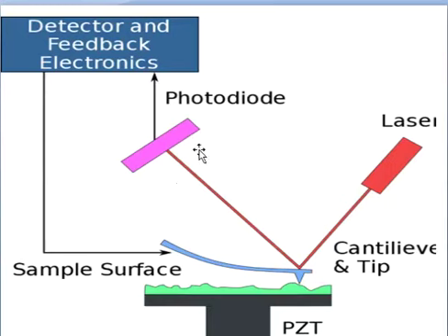As you can see here, if the position of the laser is somewhere in this direction, we can say we have a crater kind of surface, and whenever the laser is in this direction, we can say that we have humps in the surface. So based on a particular surface, we can get a particular image by combining all the graphs generated. A single line of movement of the cantilever tip generates a single graph, and this continuously goes on till a particular surface is scanned continuously.